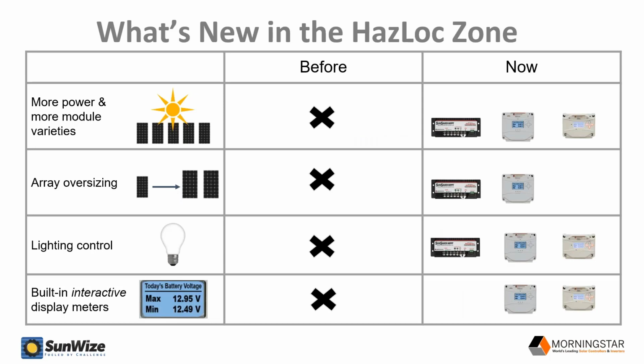So what this also provides in terms of benefits, besides just these models, is some really unique features from a technical standpoint. The first being, of course, you've got MPPT, so you have more power available with the boosting capabilities, as well as the fact that the ProStar MPPT and PWM are just larger capacity. Our Sunsaver previously reached a maximum current rating of 20 amps at 24 volts, whereas the ProStar gets up to 30 amps. And in the case of the ProStar MPPT, we have both 25 and 40 amp models available. That gives a lot of increased capacity to power generally larger systems, especially at 24 volts, which we see is really becoming a standard in this industry. Also, you gain the ability to oversize the array. PWM controllers operate at a maximum current level, but MPPT can be oversized, very similar to how grid tie inverters are often designed for 120 or 130% over their capacity because they will automatically current limit. So that gives a lot of additional reliability in terms of the sizing.